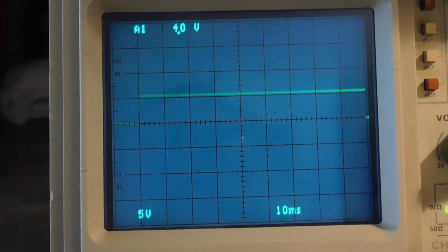Okay, what we got here is a test of the math for the PID loop. The scope has the full 100 millisecond range. Currently, the plenum pressure is 697. The set point is 707, which is about 10 torr, and it varies a little, not 698, so it varies plus or minus 1, sometimes 2.